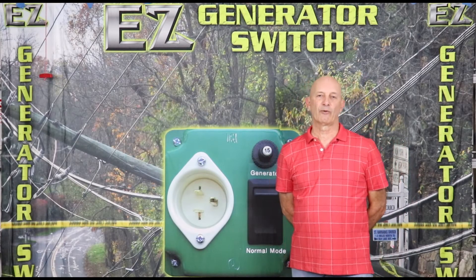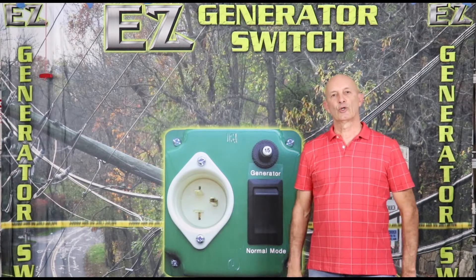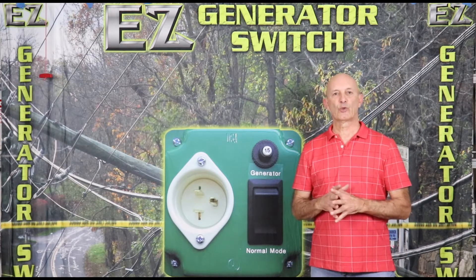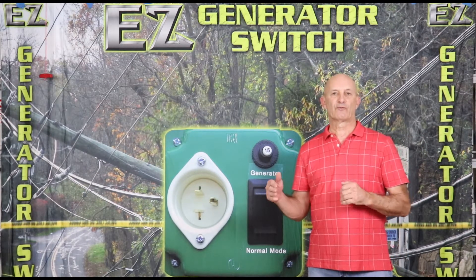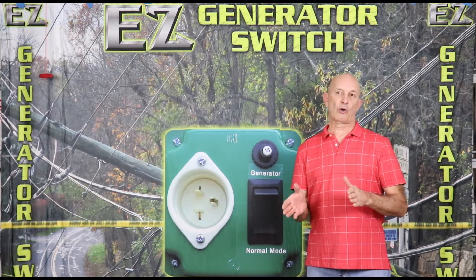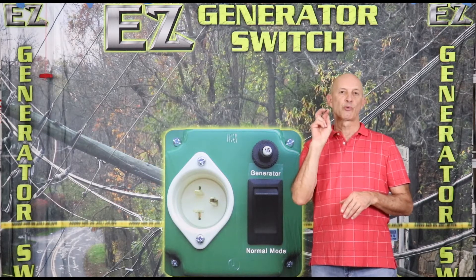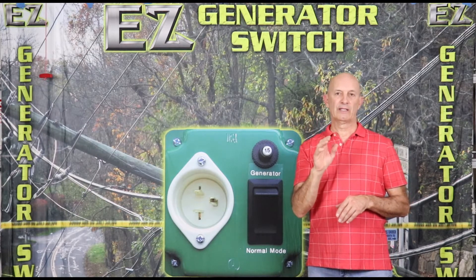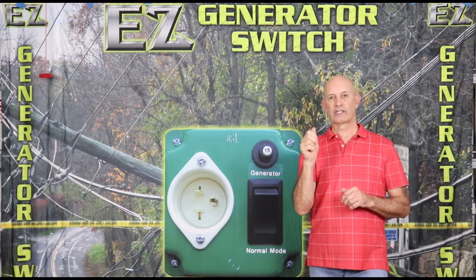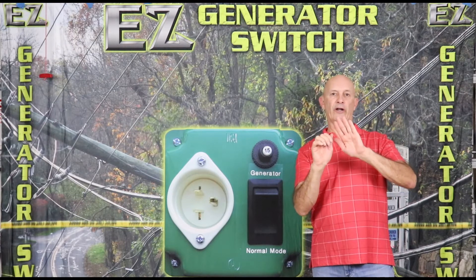Hi, my name is Kevin and I'm from EZ Generator Switch. One of the questions that we get is could I please explain the difference between the different types of transfer switches and an interlock system. So let's start with the interlock system. The interlock system requires a new breaker be put in a certain position in your panel, and that breaker can't be turned on until the main is turned off — that's why they call it an interlock.